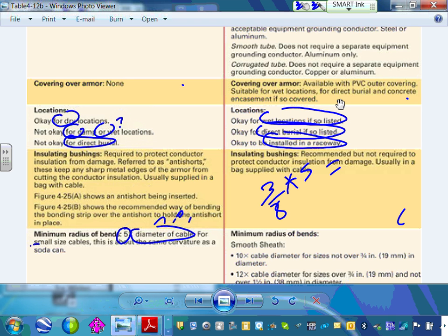Can somebody give me the math, please? How much? 1 and 7/8 inches, or 1.875. And then when you bend it, this is the bending radius. So here's your radius, guys. You start right here and make sure you bend it. You can have a larger radius, but the minimum bending radius from here is at least 1 7/8.